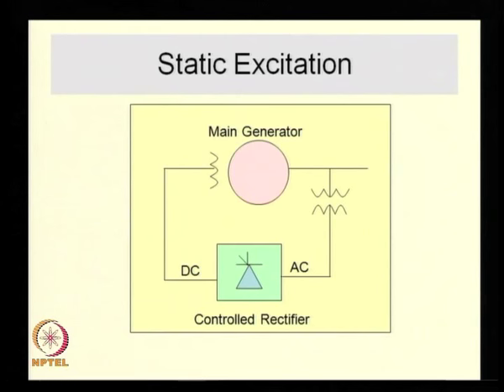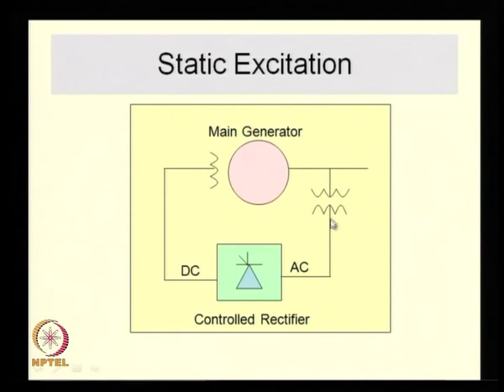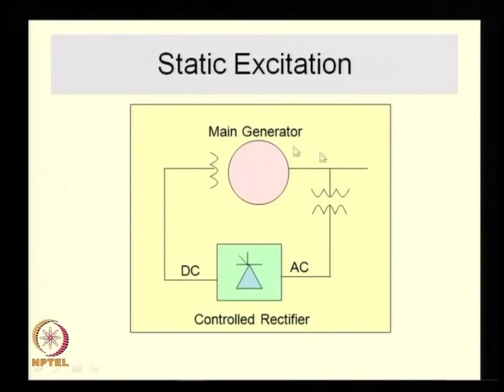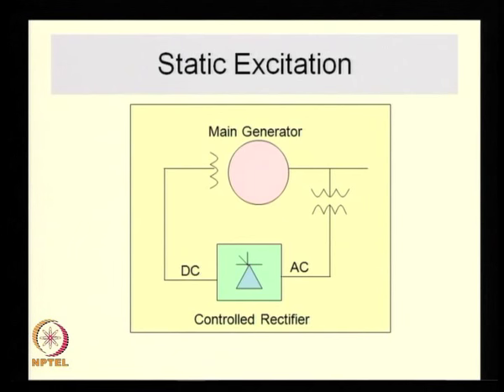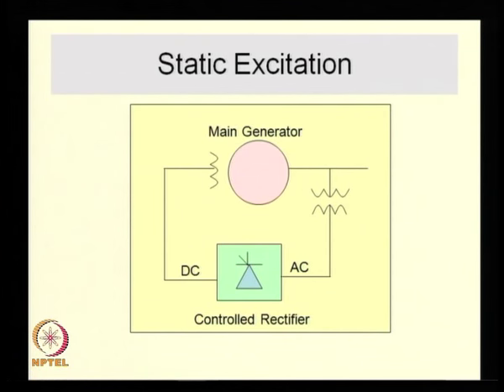The basic static excitation system studied in the previous class consists of a controlled rectifier — a thyristor-based rectifier. The AC input is derived directly from the stator voltages of the main generator, and the rectified output is fed to the field winding. This system is amenable to self-excitation, but in practice you need to initially develop some voltage across the stator windings, done using the station battery in a process known as field flashing.